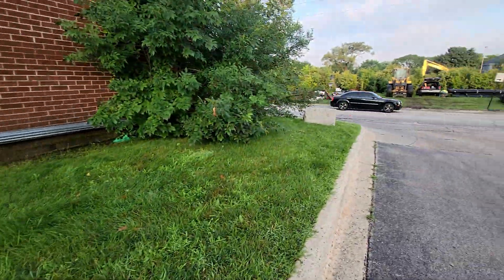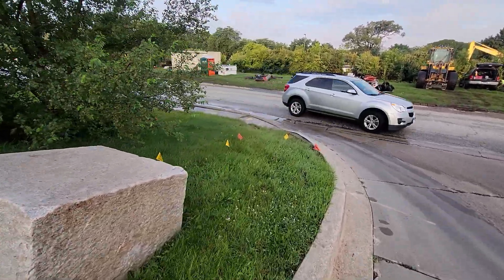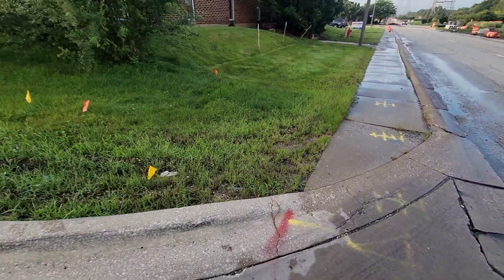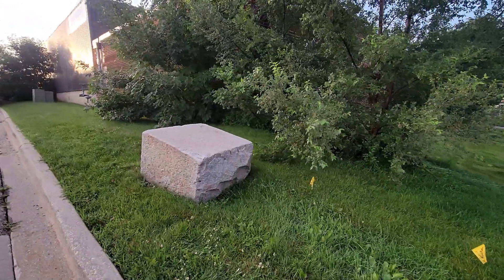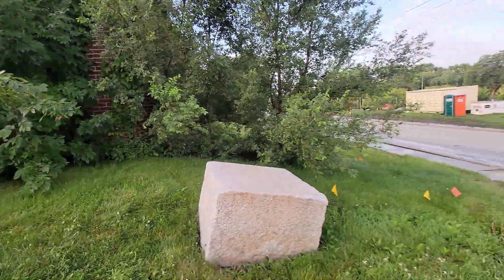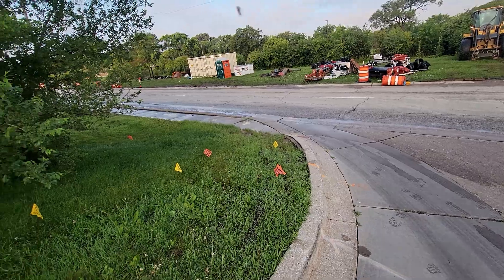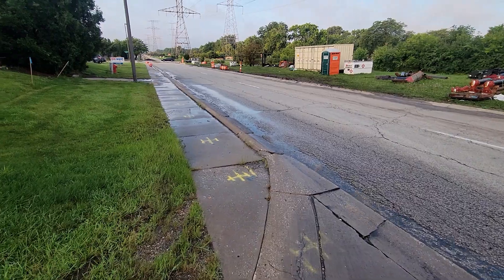Let's see what the locator got in. You can see where he has it marked out here. Here's the foundation, here's the gas service — way out there. Somebody would have marked it right by the building — 10 feet off. Who knows where it went over here in the weeds, but it's 10 feet off. Damage would have happened; they would have had to tie it in way over there on this critical main.